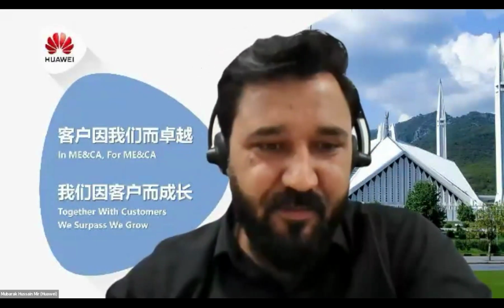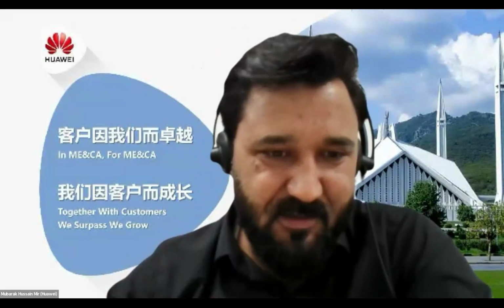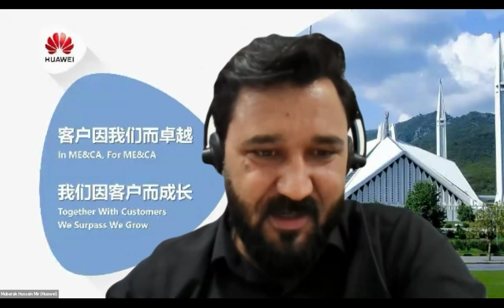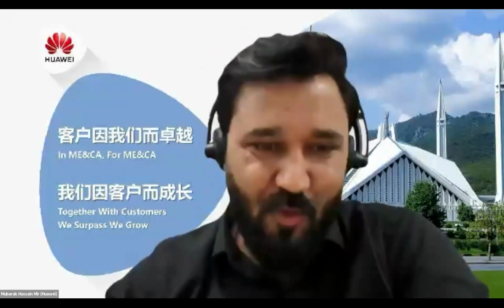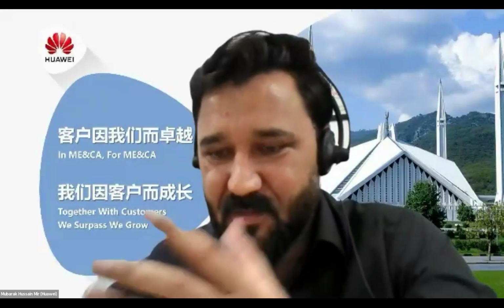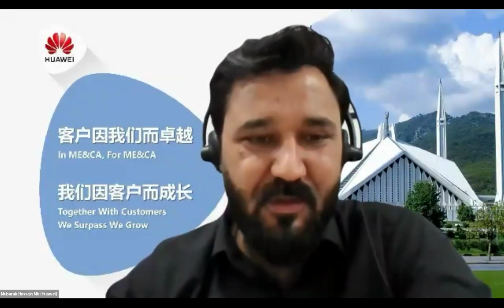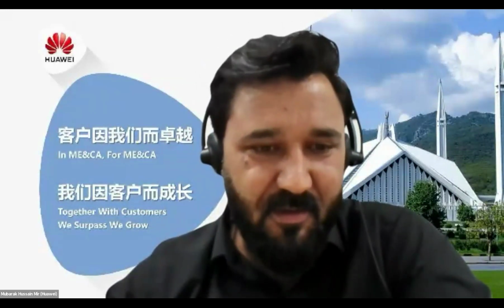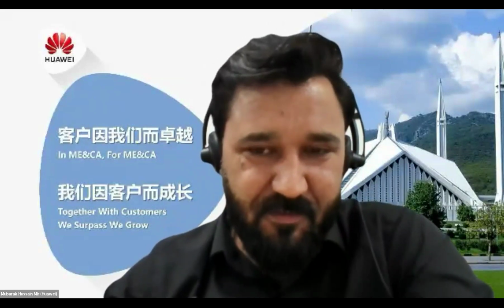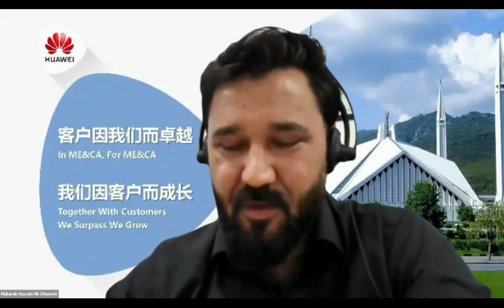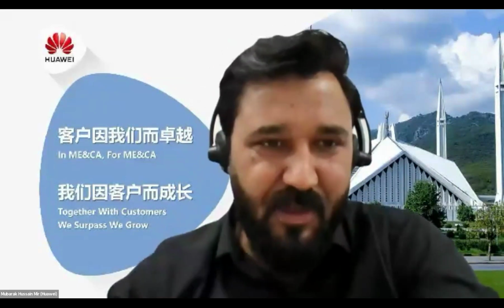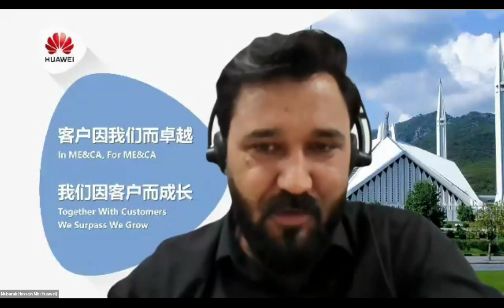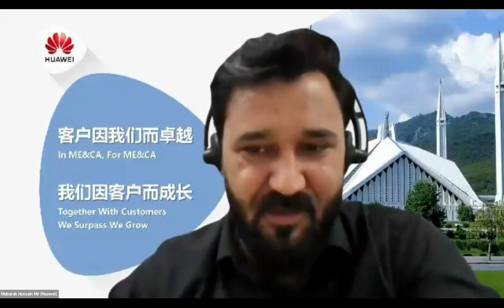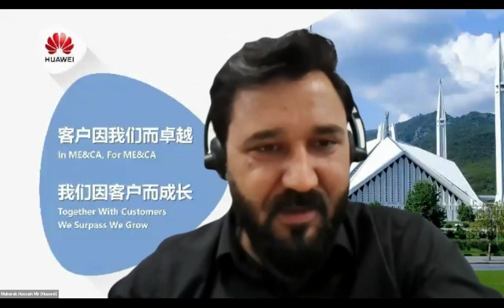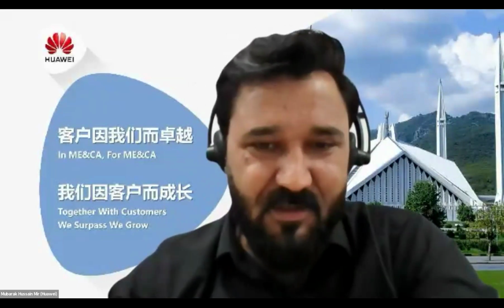So putting some very low quality breakers on the DC cable side doesn't make sense. Everyone knows, the listeners, the participants know the quality of the DC breakers available in Pakistan. So if the safety is available in the inverter, the purpose is to optimize the cost as well, not just putting it there for documentary purposes. There is a reason behind it.